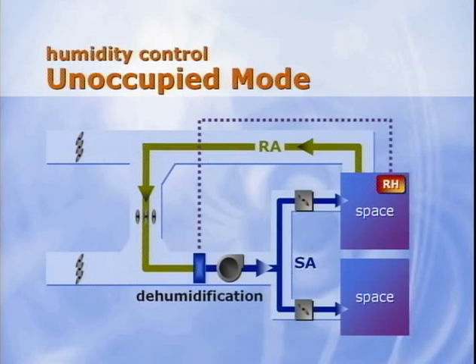However, there's typically very little sensible load in the space at this time, so the reheat coils in the VAV boxes may be activated to prevent overcooling. If a hot water heating system is used, this also requires turning on the boiler and pumps. An energy-saving alternative is to equip the rooftop unit with hot gas reheat.